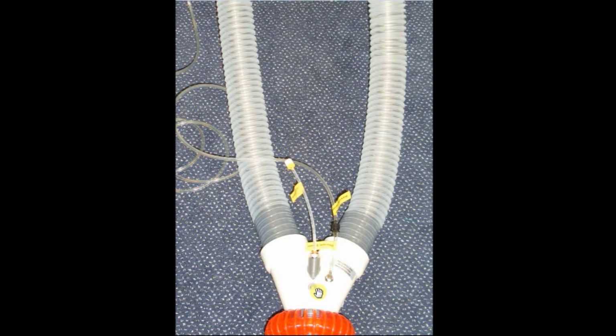In other words, if the animal breathes out and it raises the pressure here by 0.25 centimeters, this will be sensed in this sensing tube, and the piston will move up by whatever is required to return the pressure in here to zero. This servo function means that animals as small as 10 kilograms and as large as 2,000 kilograms can breathe confidently and easily on this without experiencing any resistance due to the tubes, the soda lime or the valve block.